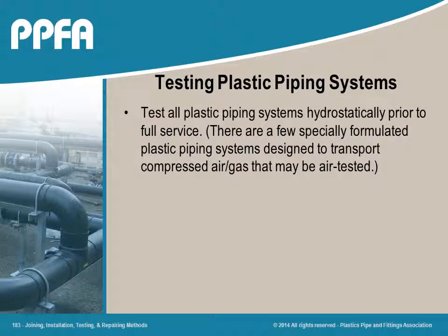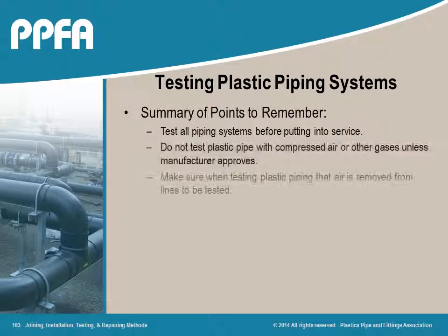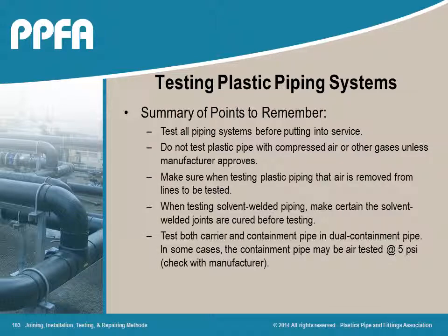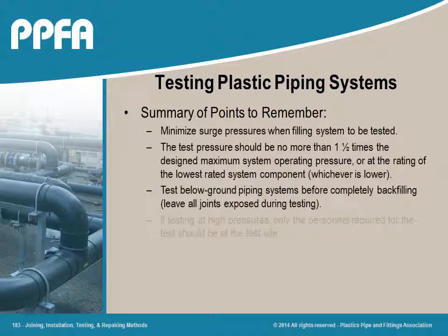Unless a manufacturer very clearly and specifically states differently, thermoplastic piping must be tested hydrostatically only using normal pipe testing procedures and must not be tested with compressed air or gas in any manner. Testing with compressed air of certain plastic piping materials can result in severe property damage and loss of life.